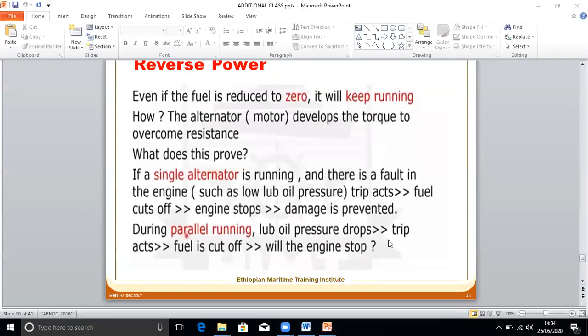This reverse power, let's see this reverse power. You see the reverse power here. Both these generators are running at 600 kilowatt, okay? And you can see here, number 2 generator has become minus 50 kilowatt. So number 1 speed setting is reduced; what we are doing is reducing the speed of number 1 generator till 0 kilowatt.